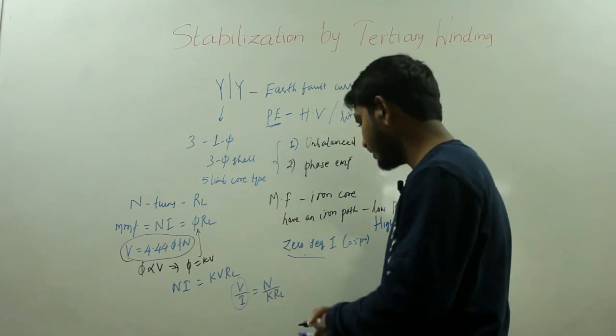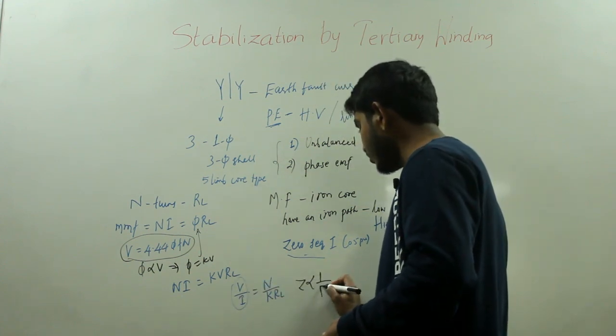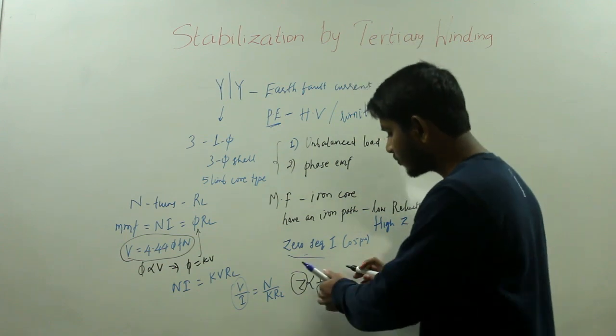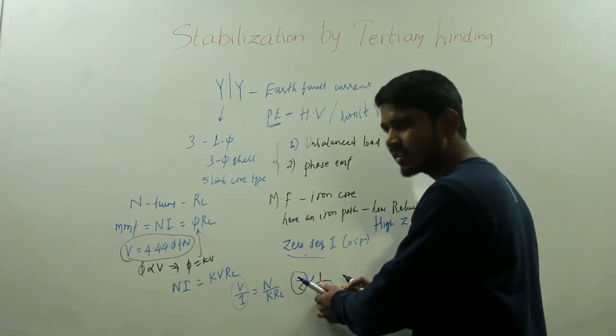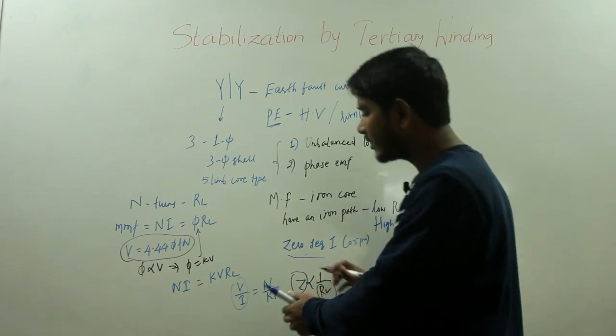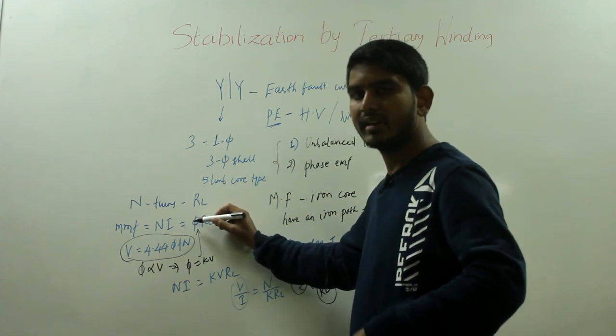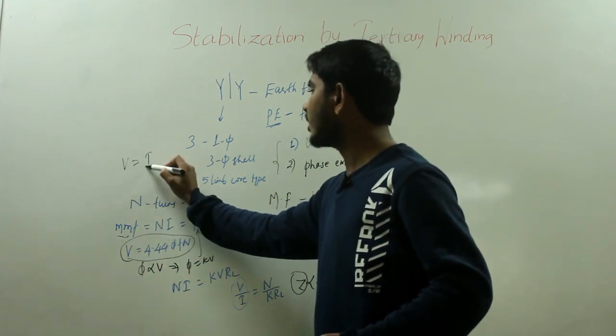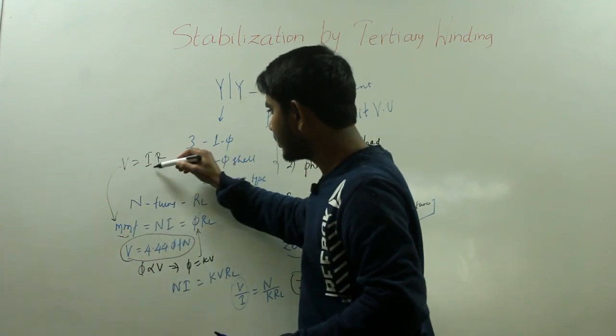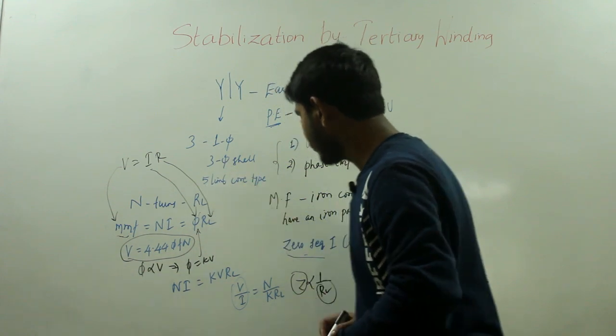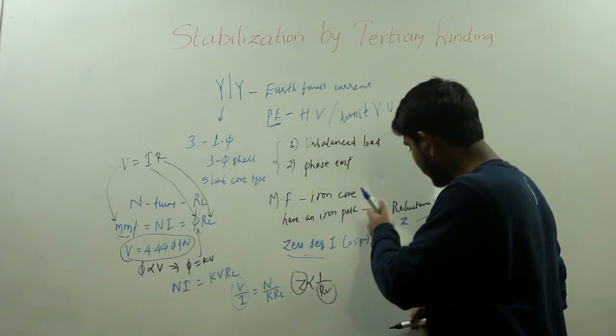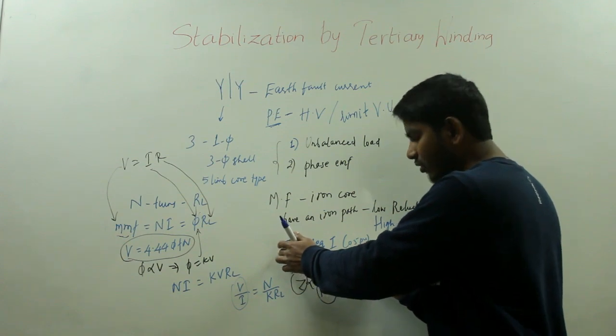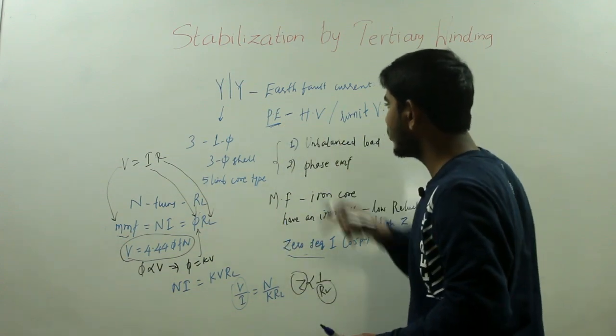V divided by I is nothing but impedance Z, so Z is inversely proportional to RL. When you have low reluctance, you will have high impedance. Comparing the magnetic circuit to an electric circuit: reluctance corresponds to resistance, magnetic flux corresponds to current, and MMF corresponds to voltage. So remember, low reluctance means high impedance, and therefore the zero sequence current will face high impedance in its path, meaning you cannot operate your protective equipment.